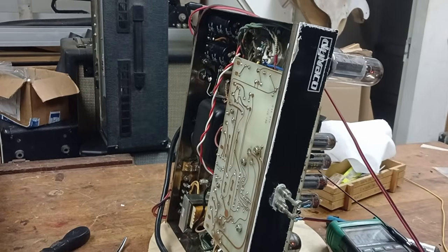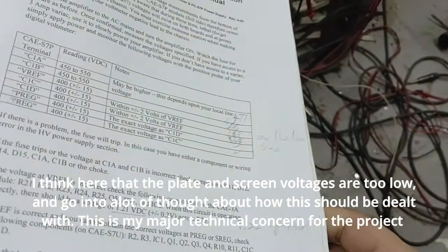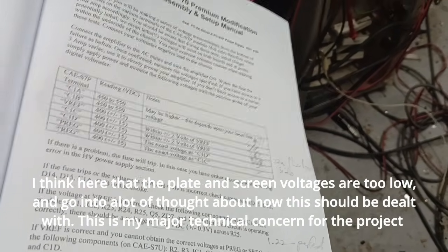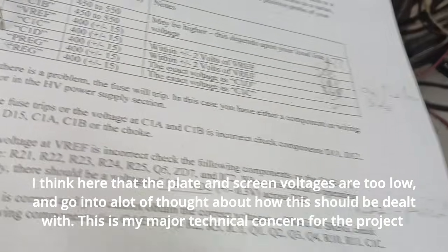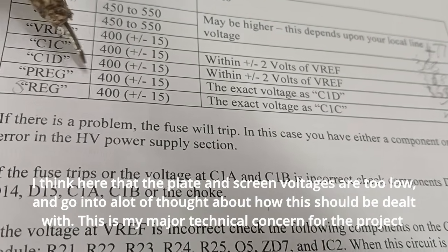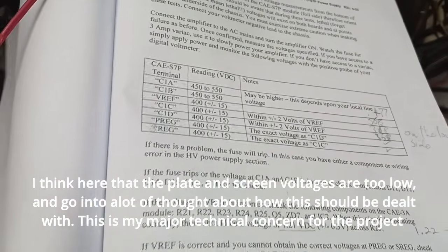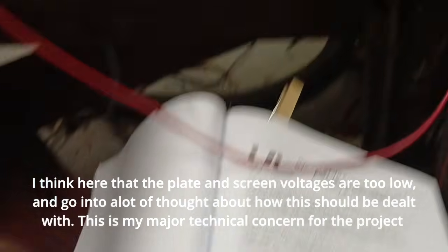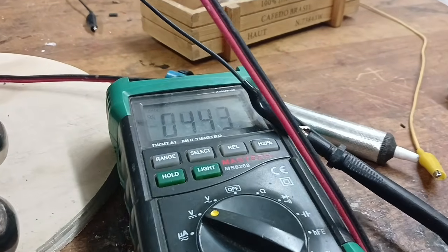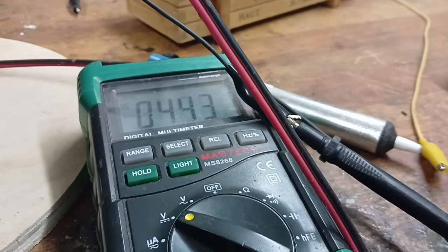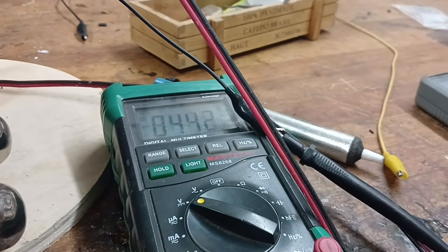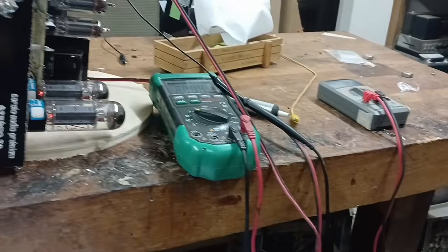Well folks, to be honest, I think I'm going to put a pause on things. I'm reviewing these voltages, and they're pretty close to the initial measurements, but I think we're too far off. This Preg and Sreg here is saying 400 volts plus or minus 15, and I'm getting a lot less than that — I'm getting 368, which is too low. Those are the regulated voltages. Now the unregulated voltage, the last one before it goes to the regulator, is 440, which is reasonable. So I think our regulator setup is losing too much voltage, about 70 volts. Something's wrong with the regulator.